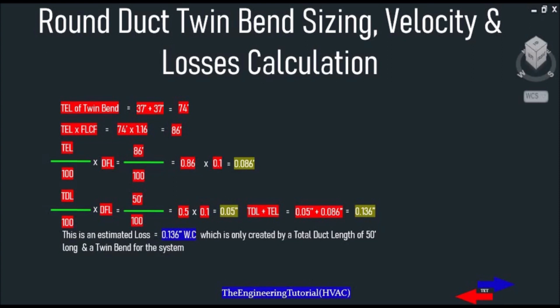Then for the main duct, by dividing the total length of the main duct — which is 50 feet — by 100 and multiplying by the design friction loss of 0.1, we get a loss of 0.05 inch of water column. Finally, adding the main duct loss of 0.05 to the twin bend equivalent length loss of 0.086, we get a total loss of 0.136 inch of water column.